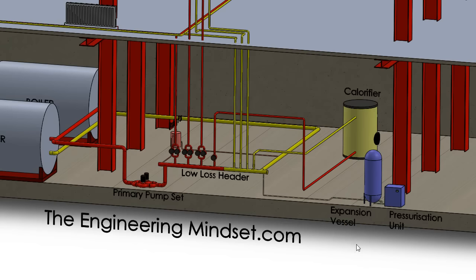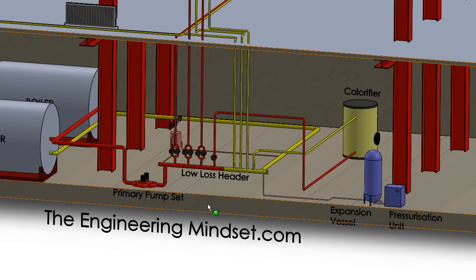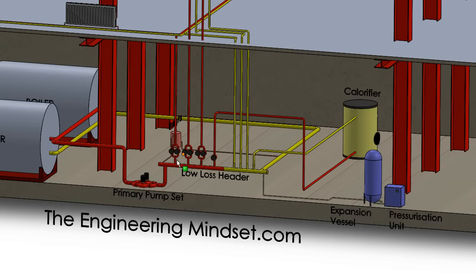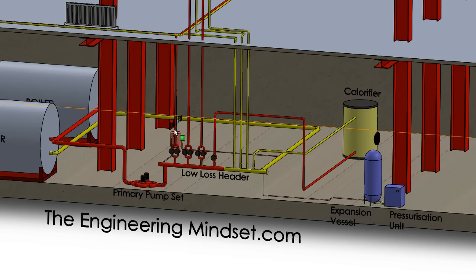Now you can also notice here we've got the expansion vessel and the pressurization unit. The pressure in the system is going to change — for example, if this pump set here is off and turns on, then the primary pump set is going to see a pressure decrease because this is opened up and there's flow there. Conversely, if those pumps stopped working and isolated this, then these pumps will see a pressure increase because there is less room for that water it's pushing to go, and so the friction is going to increase and the pressure will build up. Similarly, when the water in this loop increases or decreases in temperature, it's going to change in density, and that's also going to affect the pressure.